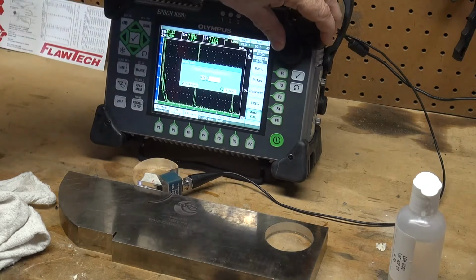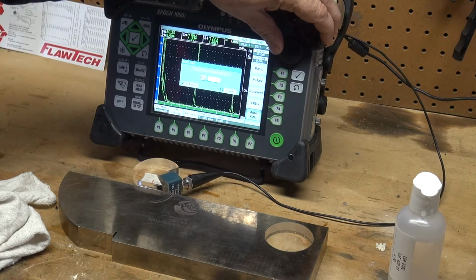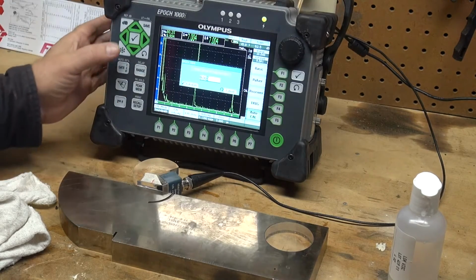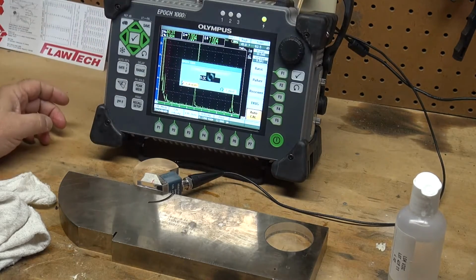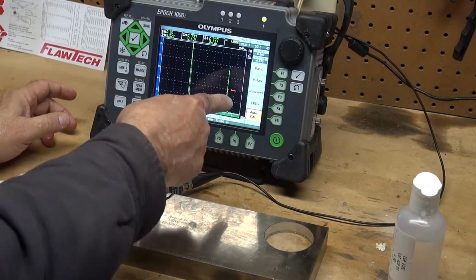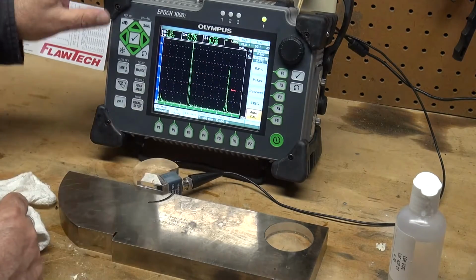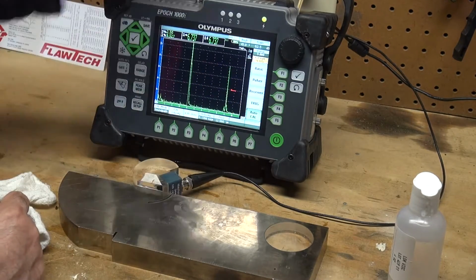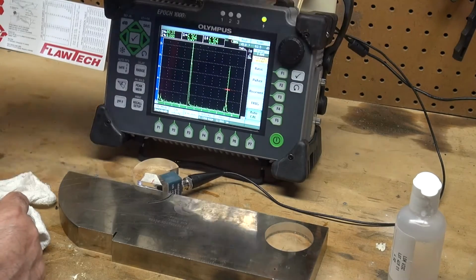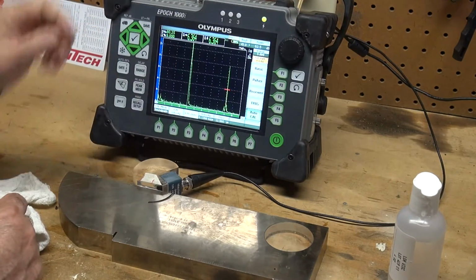9 inches. And by hitting the check, it is calculating. Calibration is done. You see the cal has disappeared. Let me take my gate and slide it over that 9-inch radius. My sound path is 9 inches.